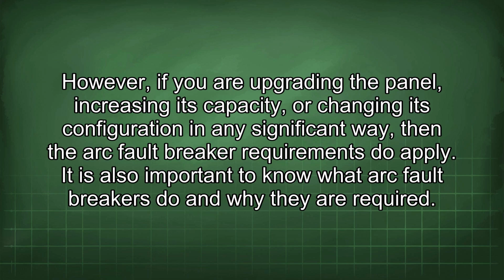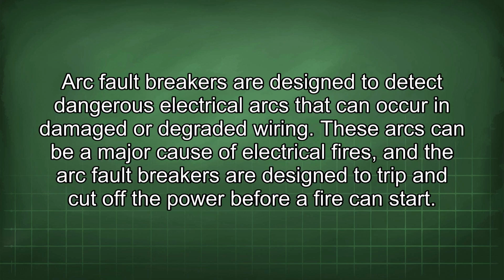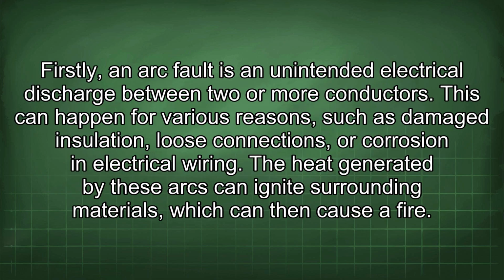It is also important to know what arc fault breakers do and why they are required. Arc fault breakers are designed to detect dangerous electrical arcs that can occur in damaged or degraded wiring. These arcs can be a major cause of electrical fires, and the arc fault breakers are designed to trip and cut off the power before a fire can start. Firstly, an arc fault is an unintended electrical discharge between two or more conductors. This can happen for various reasons, such as damaged insulation, loose connections, or corrosion in electrical wiring. The heat generated by these arcs can ignite surrounding materials, which can then cause a fire.